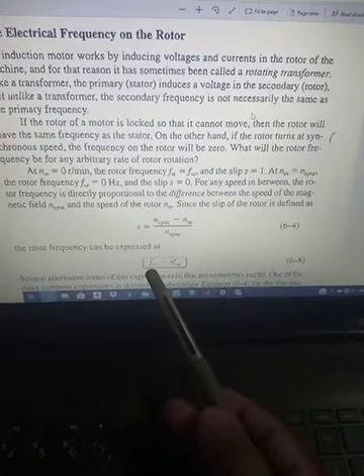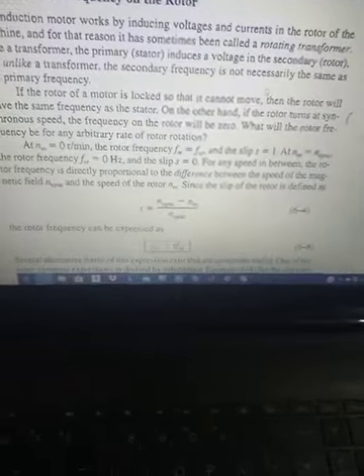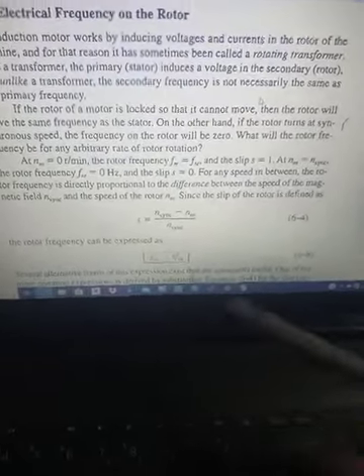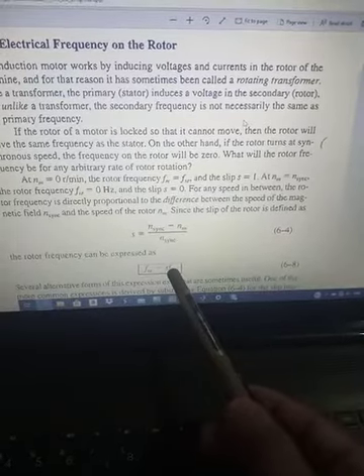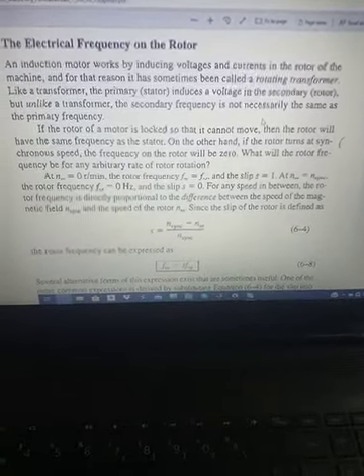The rotor's electrical frequency equals the slip multiplied by the stator's electrical frequency. When the rotor is stationary, the slip is 1, so the rotor and stator frequency are equal. When the rotor and stator magnetic field rotate at the same speed, the rotor frequency becomes zero.